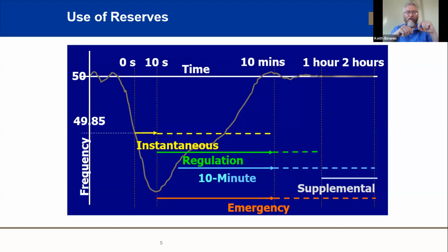Instantaneous reserve is predominantly, particularly when dealing with the coal power stations - they provide instantaneous reserve, which is the ability to increase or reduce steam generation by a governor on site in the turbine. Essentially, you're just ramping up a little extra power by pushing through more steam. The governors are installed as part of the process when you build the plant, but that is a bit of an efficiency loss, so it's built into the cost of building these power stations to have this governor capability, which can provide more or less steam at the coal power station.